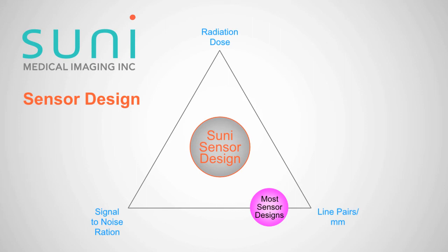If you make the pixel very small, you have a good ability to detect high line-pairs-per-mm, but you sacrifice your signal-to-noise ratio. If you make the pixel large, you pay a price on line-pairs-per-mm performance but you gain on the signal-to-noise ratio.